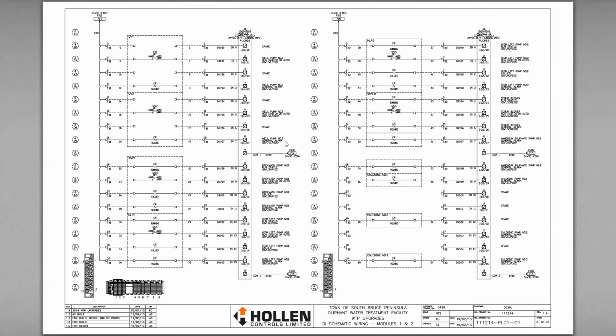Moving on from power, you can see now we're getting into the IO wiring for this site. So we have a DC input card. This is an Allen Bradley 1769 IQ16. If you were to look that up, that's a CompactLogix IO module, a DC 16-point sinking input card. You can see the second module is the same card. What we have here are IO points and how they're electrically wired up.